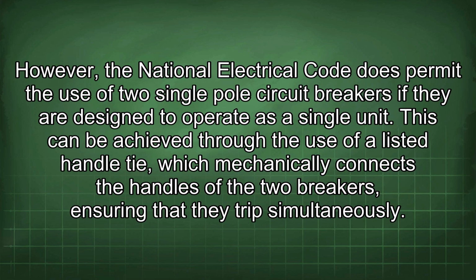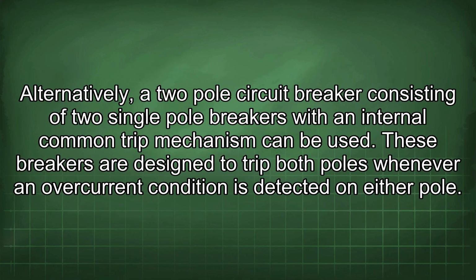However, the National Electrical Code does permit the use of two single-pole circuit breakers if they are designed to operate as a single unit. This can be achieved through the use of a listed handle tie, which mechanically connects the handles of the two breakers, ensuring that they trip simultaneously. Alternatively, a two-pole circuit breaker consisting of two single-pole breakers with an internal common trip mechanism can be used. These breakers are designed to trip both poles whenever an overcurrent condition is detected on either pole.